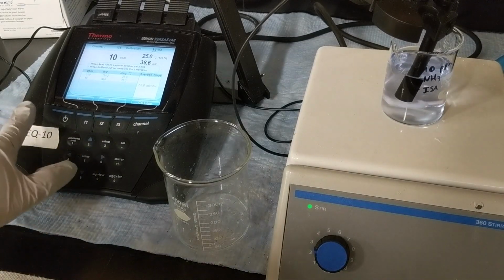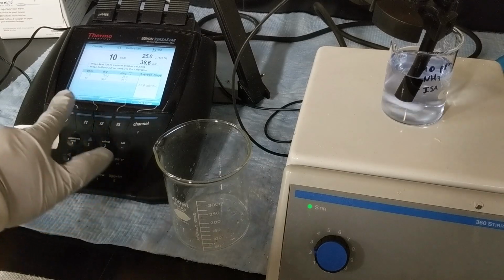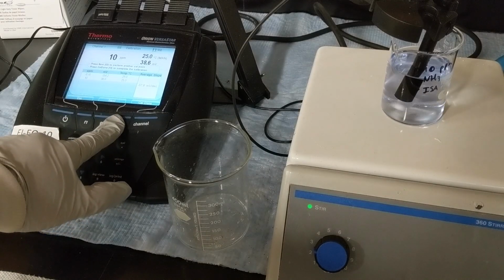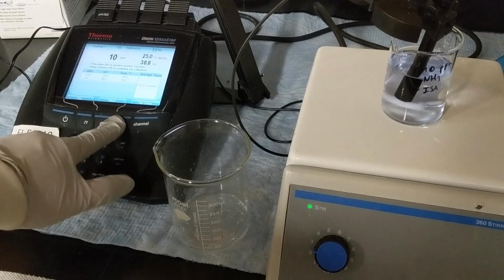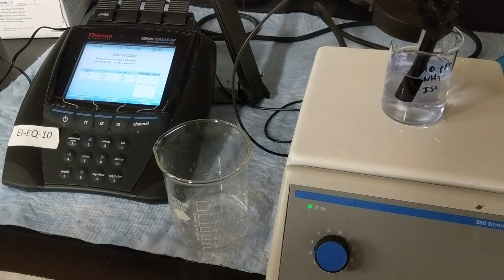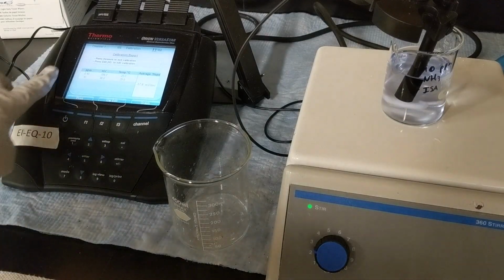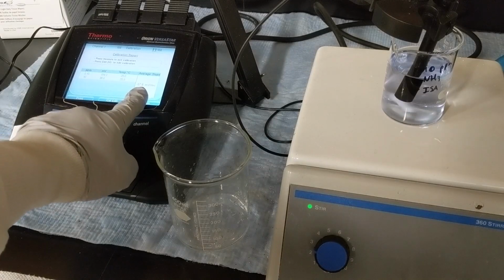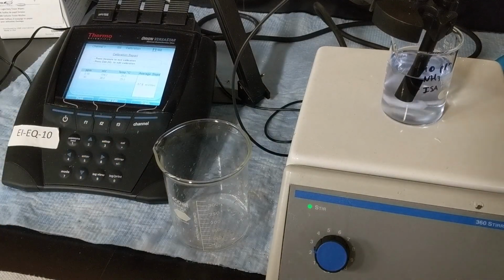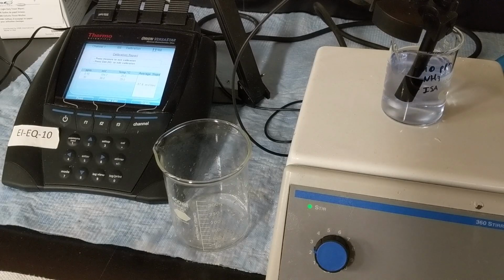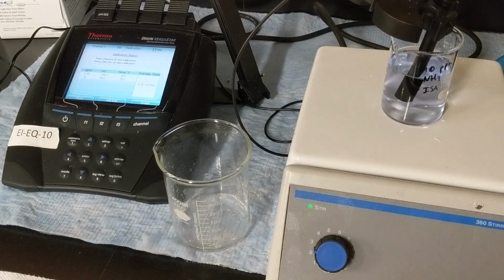And now, again, we have escape, next, and cal done, and so since it's only a 2-point calibration, I'm going to hit F3 for cal done. And it's good to look at this average slope. I don't know if you can see it on the video, it's showing me negative 57.8 millivolts per decade. It should be around negative 59, so that's not too bad from where it should be.